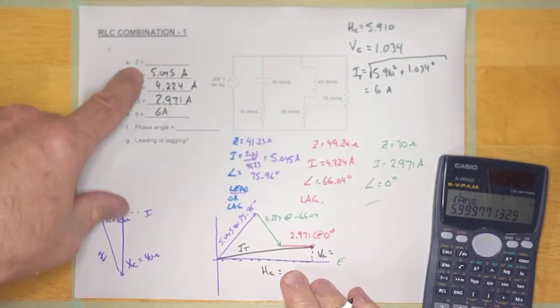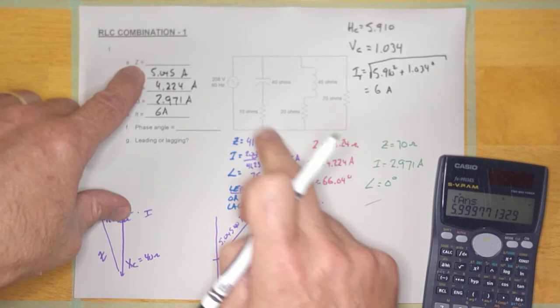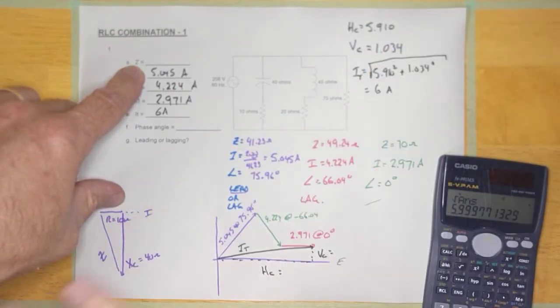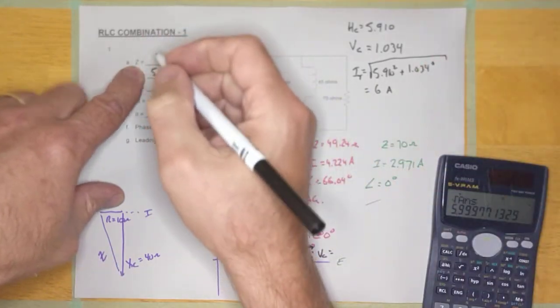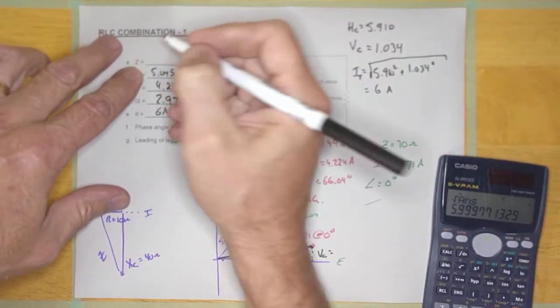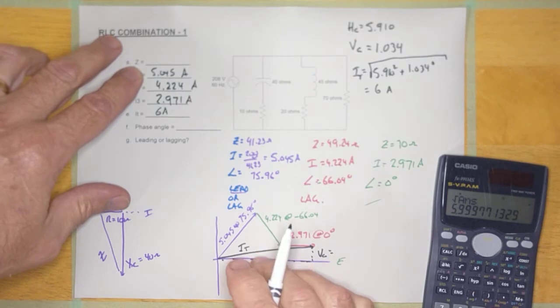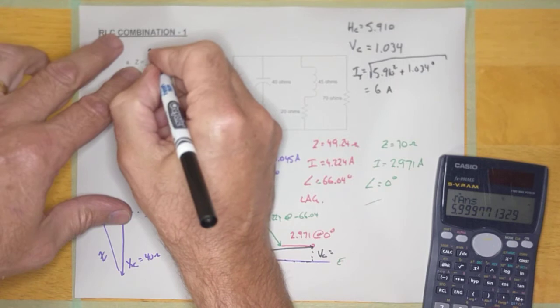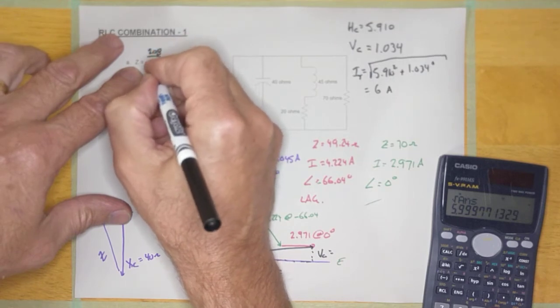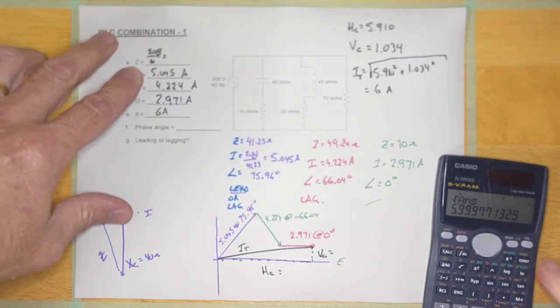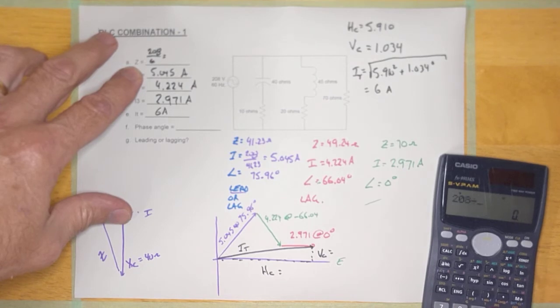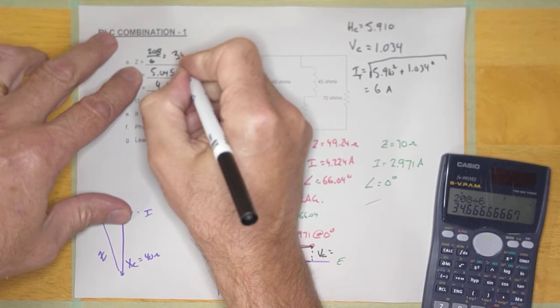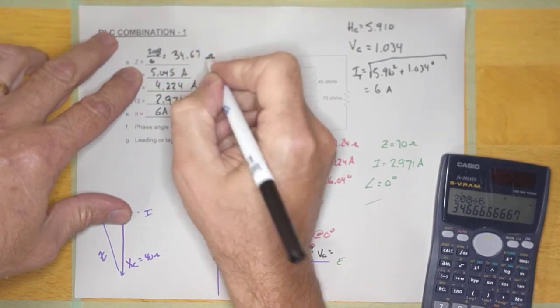The next thing we're going to calculate is the impedance. It is a parallel circuit, so the only way to calculate impedance is with Ohm's Law — Z = E over I. E is 208 and I is 6, so 208 divided by 6 equals 34.67 ohms.